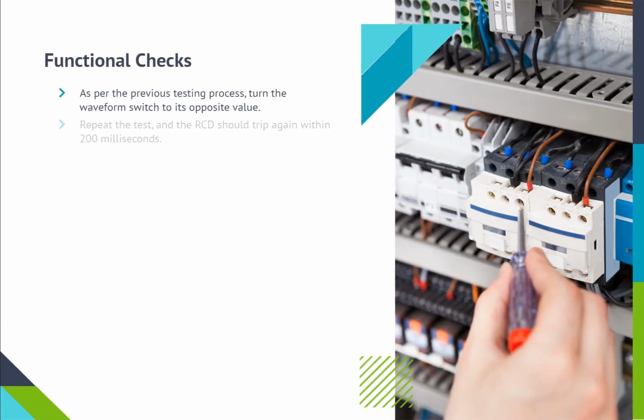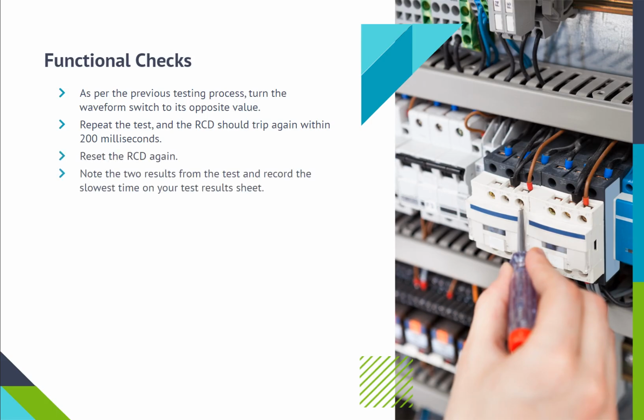As per the previous testing process, turn the waveform switch to its opposite value. Repeat the test, and the RCD should trip again within 200 milliseconds. Reset the RCD again. Note the two results from the test, and record the slowest time on your test results sheet.